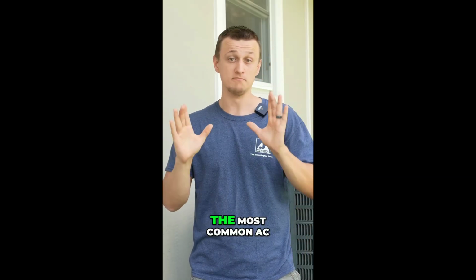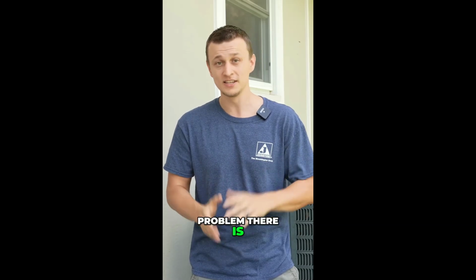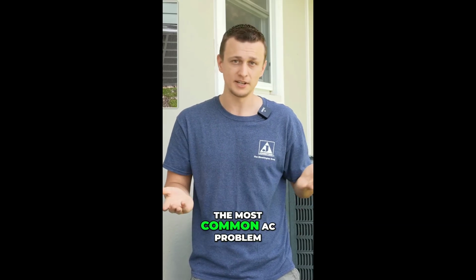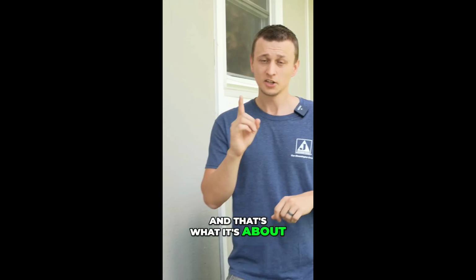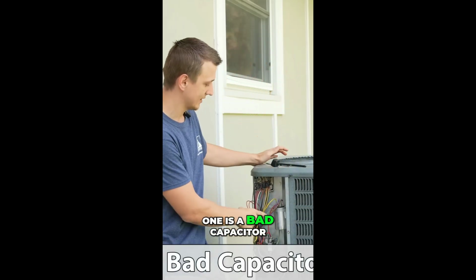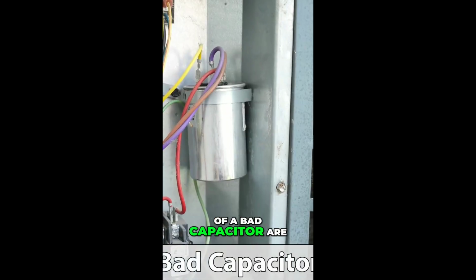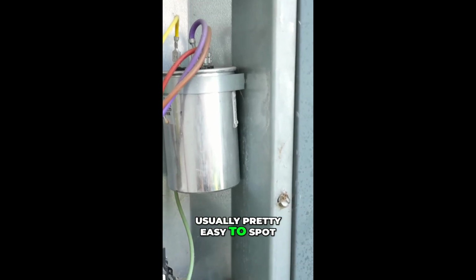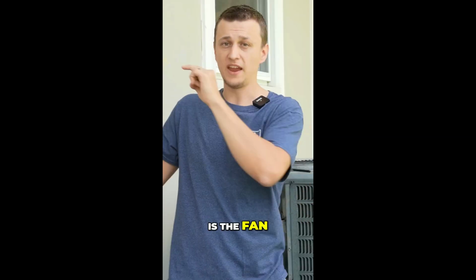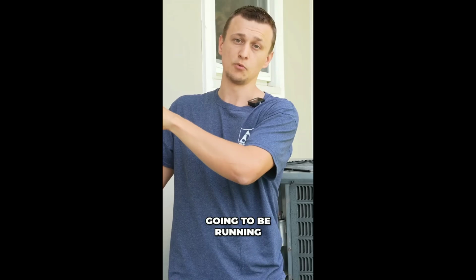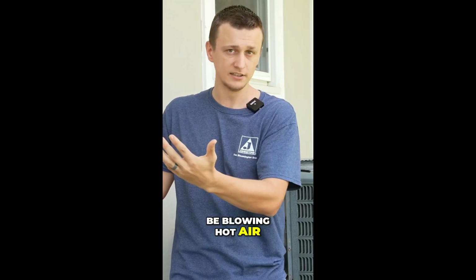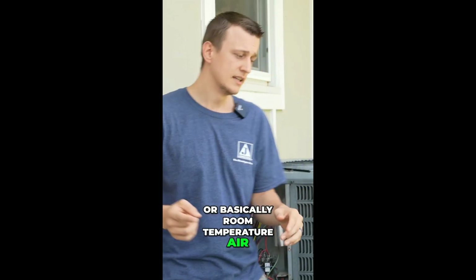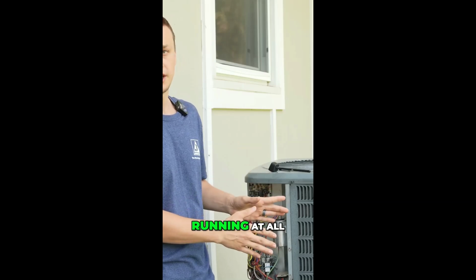Problem number one. This is by far the most common AC problem there is. In fact, I even have a video called The Most Common AC Problem, and that's what it's about. Problem number one is a bad capacitor. The symptoms of a bad capacitor are usually pretty easy to spot. What will happen is the fan inside the house is going to be running, but it's going to be blowing hot air, or basically room temperature air, and the unit outside will not be running at all.